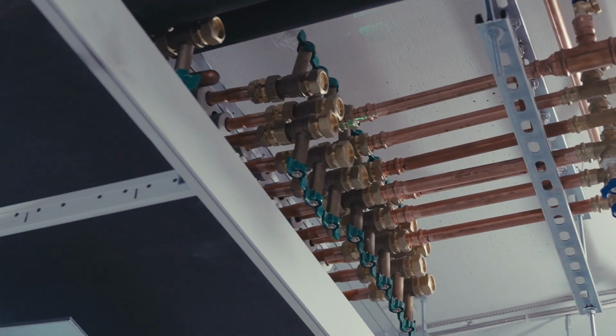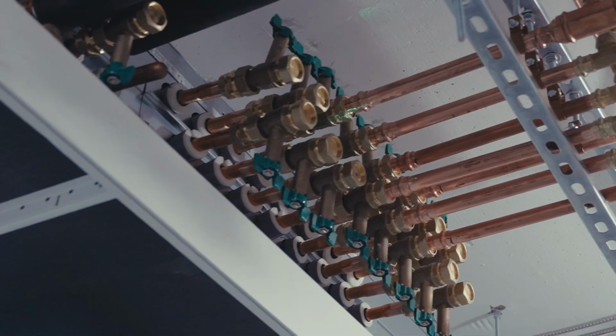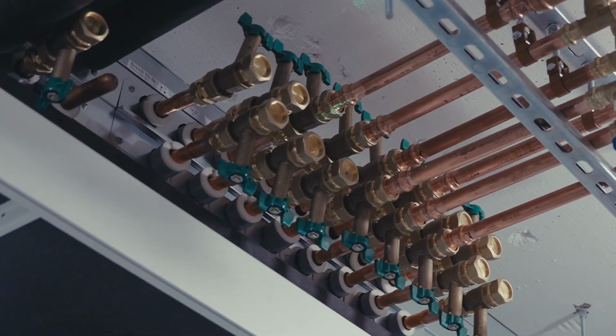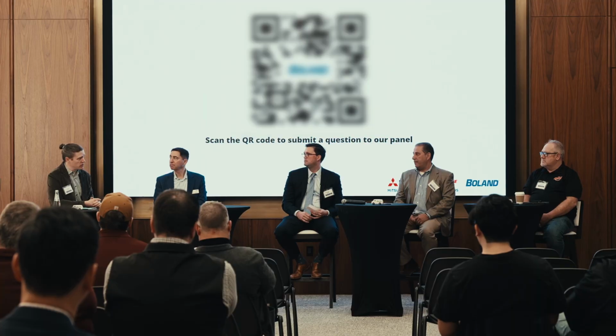the system is much more flexible with regards to using hydronic piping downstream of the branch control box. So it's much easier to change out fan coil units, to move those locations, to move that hydronic piping. And I think we can talk a little bit about the differences between how the refrigerant and hydronic piping are installed. So that would be the biggest thing with respect to planning for an office environment. And I know we're going to talk about lessons learned in a little bit.